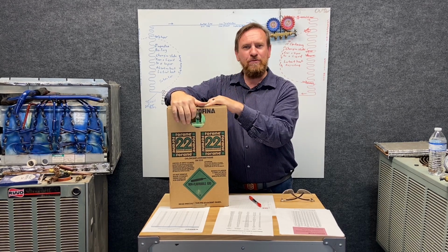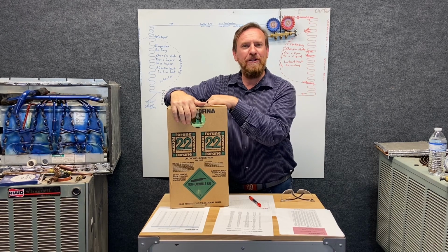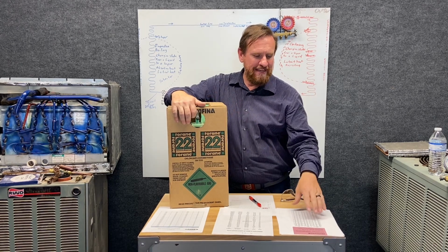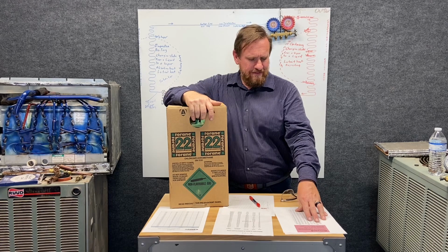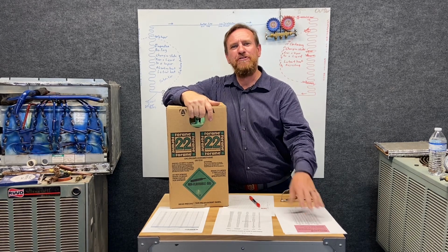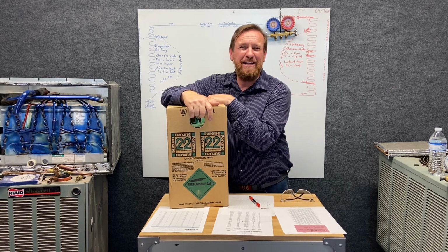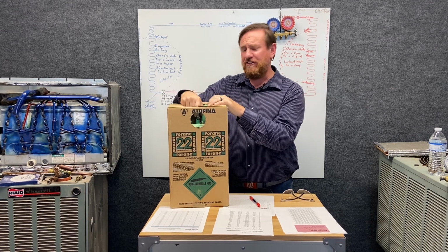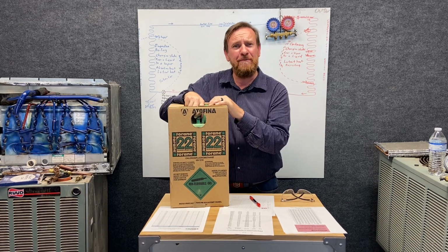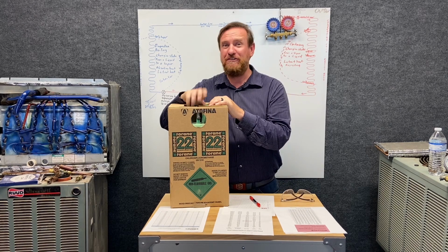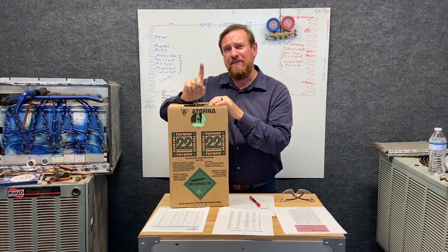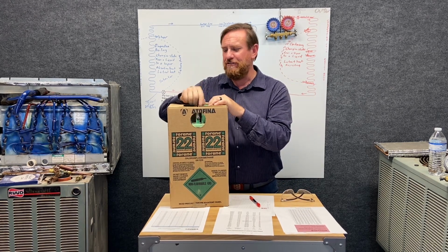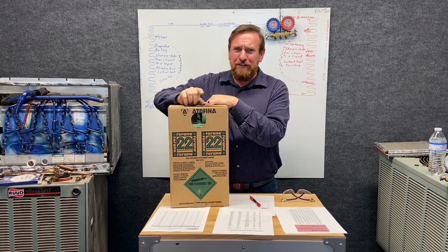But it's an HCFC22. It's very popular. It has a low boiling point. We can actually map this out at 0 psi gauge. At atmospheric pressure, this refrigerant boils at approximately minus 40 degrees Fahrenheit, which means if I was to turn this upside down where liquid refrigerant comes out and open this valve, which is illegal and you should never do that according to the EPA, and they will fine you, or could fine you anyways, and destroy the ozone layer.